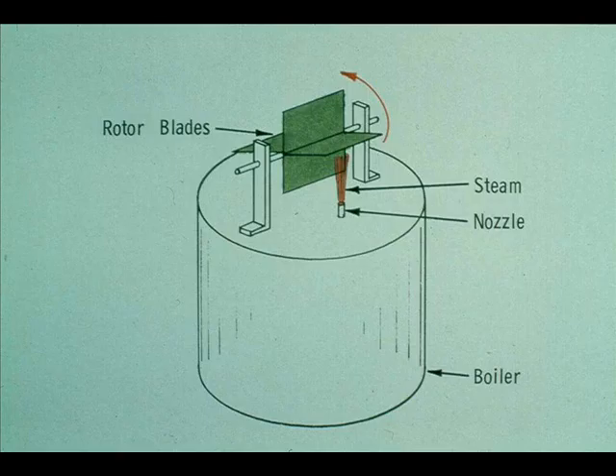Now that you have seen some examples of steam turbines in operation, let's take a closer look at the turbine itself. There are two basic types: impulse and reaction. The most common type, the impulse turbine, is shown here. The shaft is turned by the force of steam striking the blades, or buckets as they are sometimes called. It's very similar to the way a water wheel works.